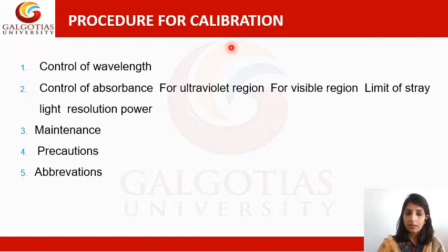Then what is the procedure for calibration? If we are performing the calibration of UV visible spectrophotometer, we need to look over certain parameters: the control of wavelength, the wavelength scale we need to calibrate, the control of absorbance, then the limit of stray light and the control of resolution power. These are the parameters that we need to calibrate before using the UV visible spectrophotometer. Also, we will check the slit width of the UV visible spectrophotometer, and then the maintenance of your spectrophotometer, the precautions you need to take, and certain abbreviations.